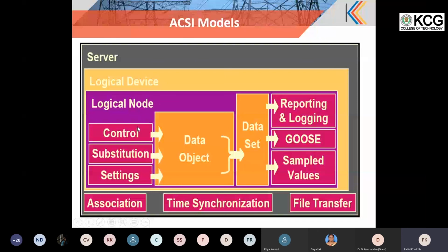Then you can have a substitution. Substitution is nothing but, you have process data coming up, and if there is some problem with the process data, every time you will be getting raw data. In that scenario, you want a substituted value to be enabled with the process element, with the transducer. That is done using the substitution.